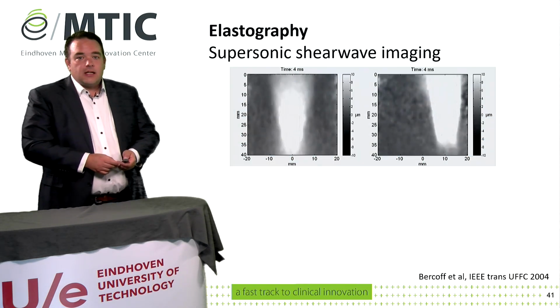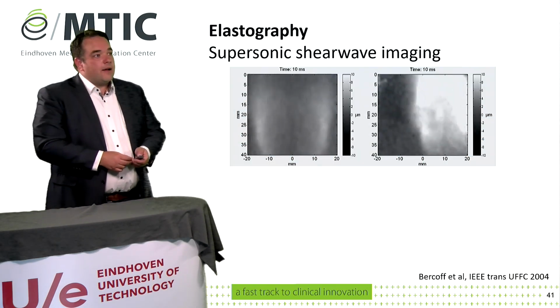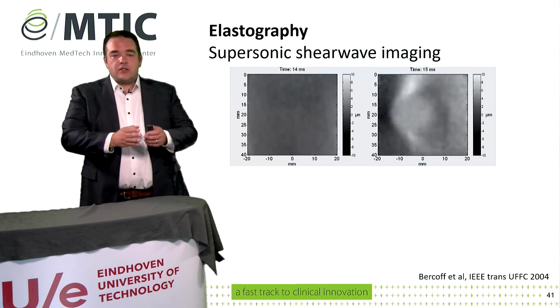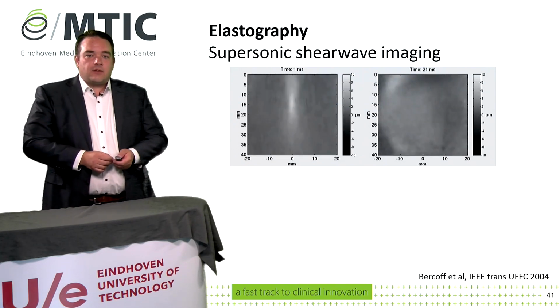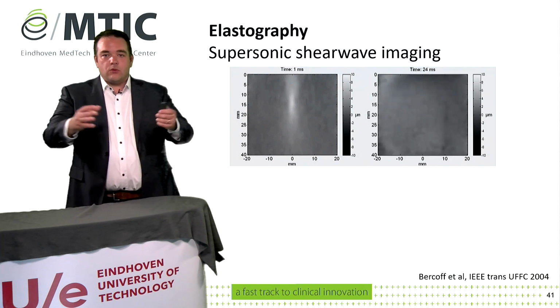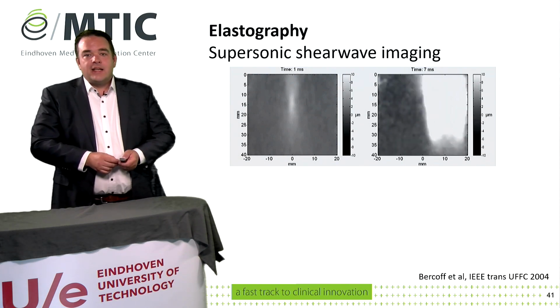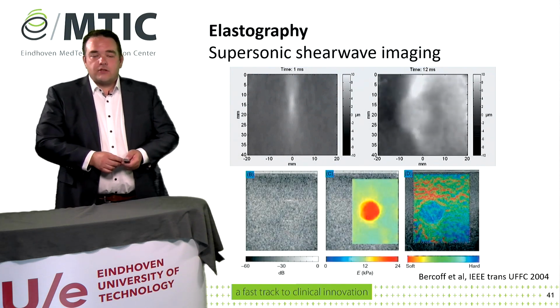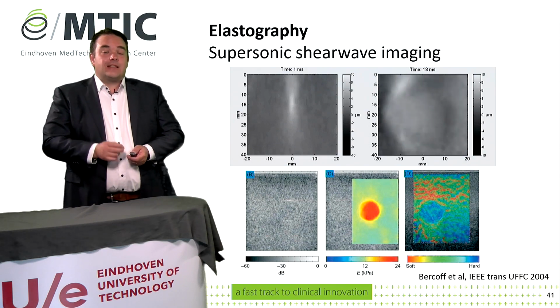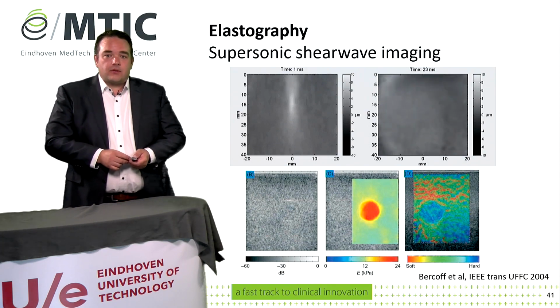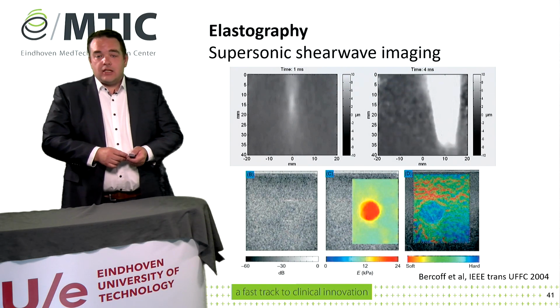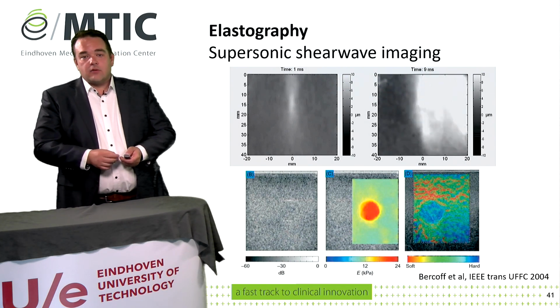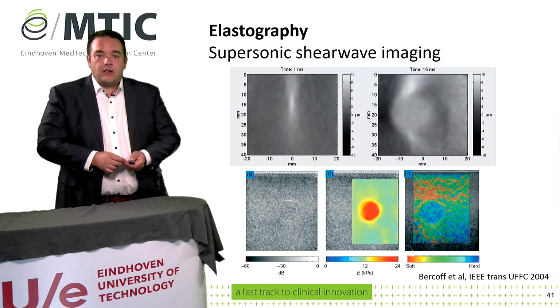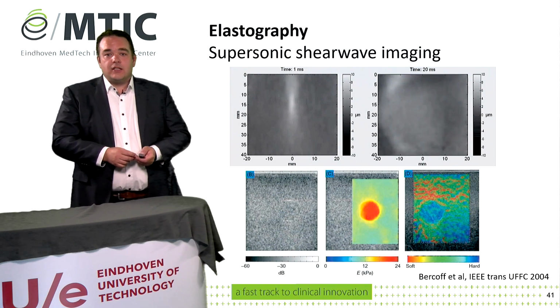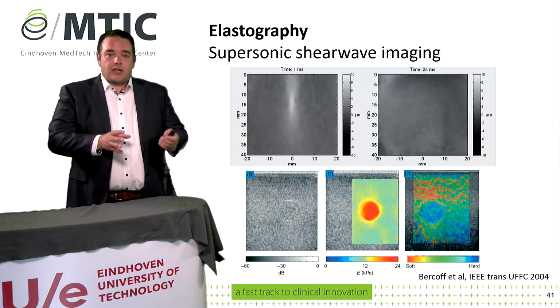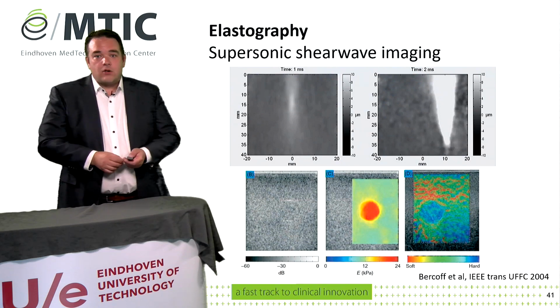Here are two nice movies from that group. On the left, a homogeneous phantom, and you see the shear wave propagating. On the right, a phantom again with an inclusion, and you see the wavefront being distorted. If you track the wavefront, you know the shear speed, and if you know the shear speed, you can calculate the elasticity parameter, the Young's modulus. So now you can see this inclusion in the elastogram, but even with a numerical value for the elasticity. Not only is the contrast better, we now also have quantitative numbers.